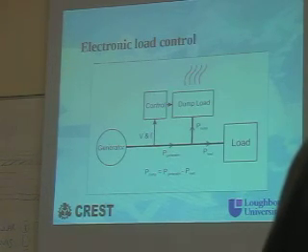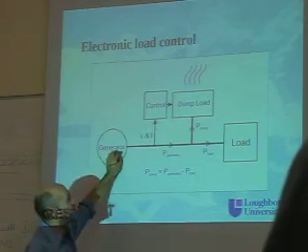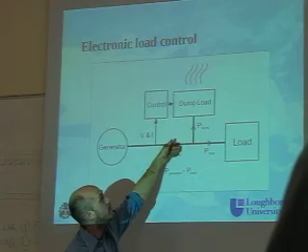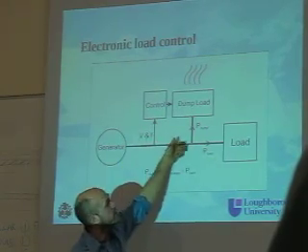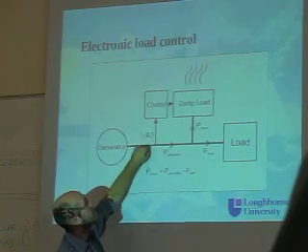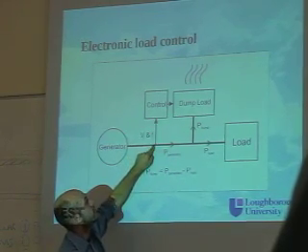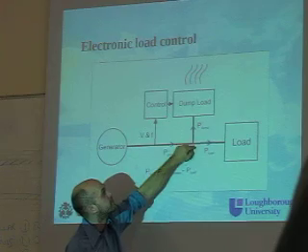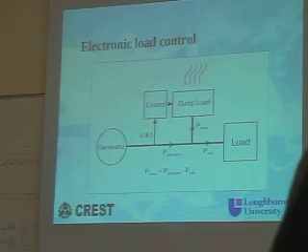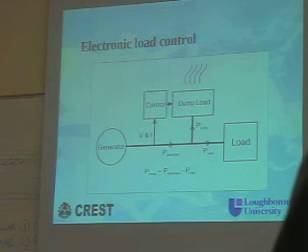So just a block diagram of that, you've got your generator, it's shoving out a certain amount of power. Say it's putting out 6 kilowatts, your load is 5 kilowatts, you have to dump 1 kilowatt. And in order to follow it, you have a control system which looks at the voltage and the frequency and controls the dump load. Generally dumped as heat. It's quite difficult to use that heat usefully. I've seen it where they've dried fish on it. But apart from that, generally it's wasted, or hot water sometimes.